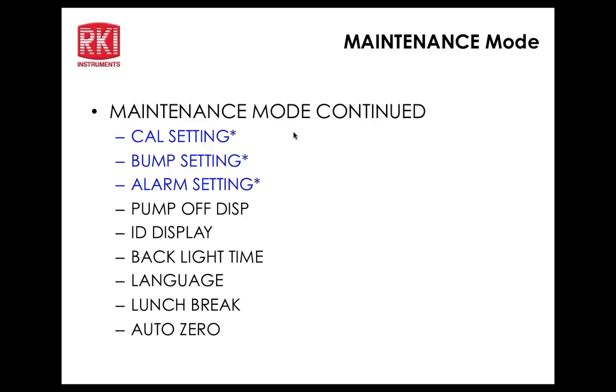We can set the bump reminder, the bump interval, how often you want the bump activated, and bump expired action, very much like the other instruments: cannot use, confirm to use, or ignore. Then bump check gas, and escape. We're back to the main maintenance menu.